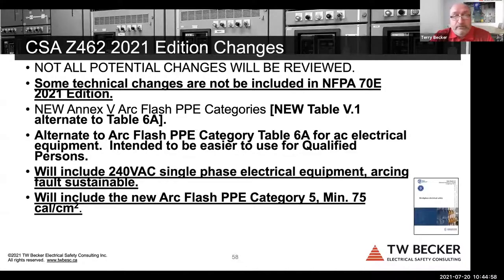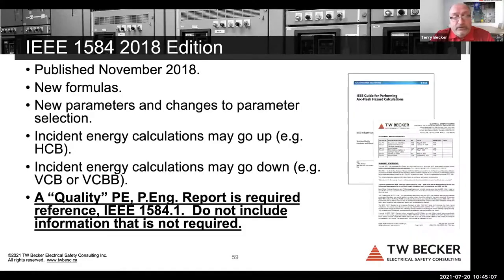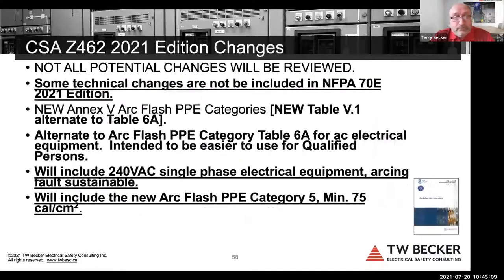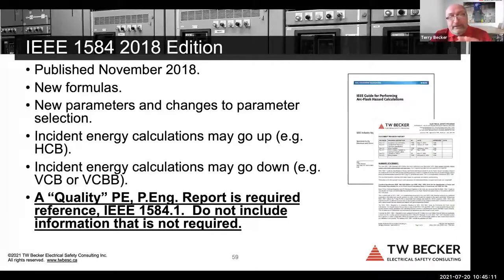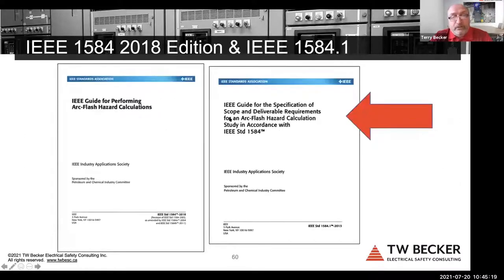And currently, until I get better information, I would not support that 240 volt single phase can sustain an abnormal arcing fault and become an arc flash. The new 1584, again, I'm looking at the time, and I'm always running short when I talk, but the key here is we need quality engineering reports. And right now, a lot of engineers do not know that IEEE 1584.1 exists. And 1584.1 is an amazing document. Published in 2013, it's been around a while.